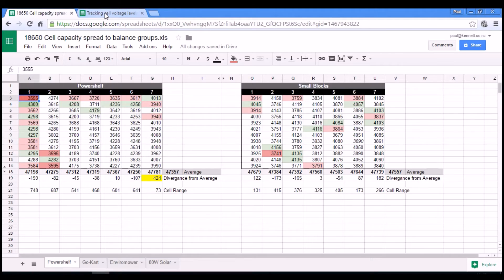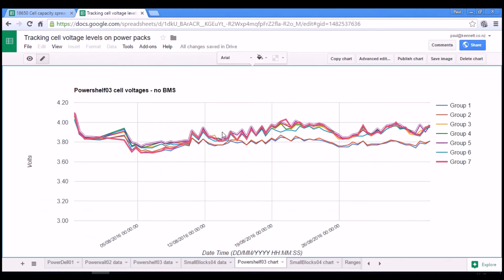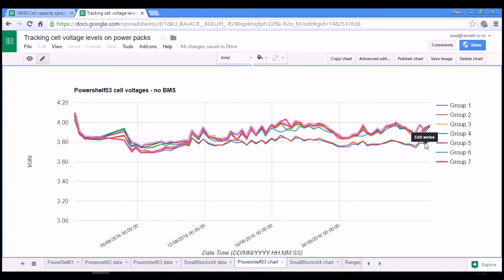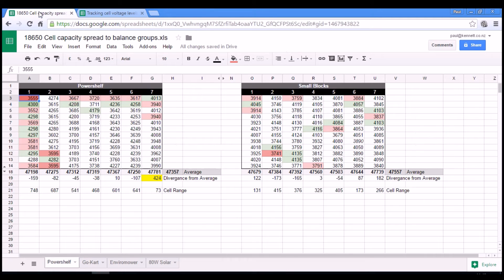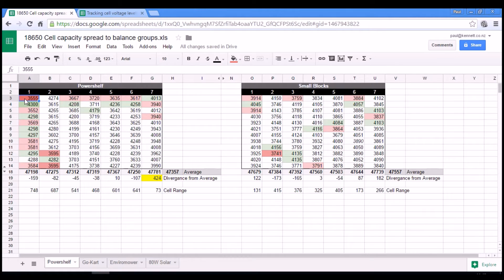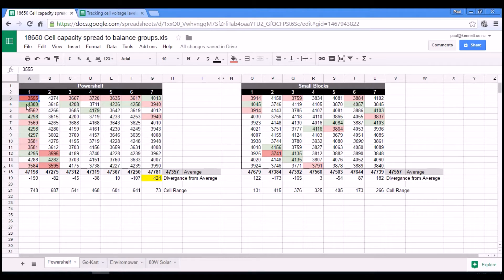And just to jump back to the actual chart of capacities that we were looking at last week. So groups one and two are these two ones that are drifting low. And if we look over here, groups one and two are the ones with the lowest capacity cells within them. They also happen to contain the highest capacity cells within them.